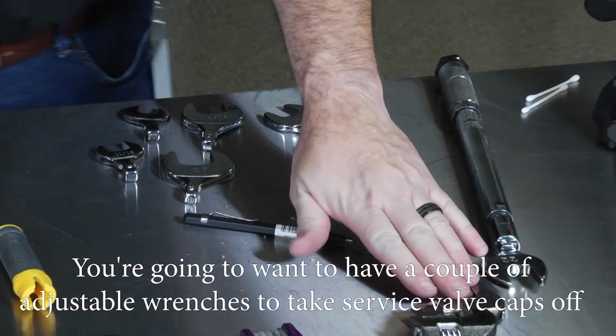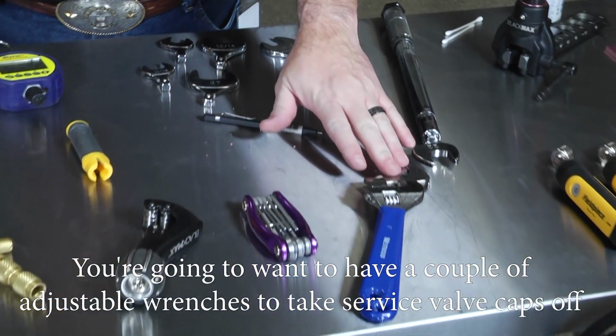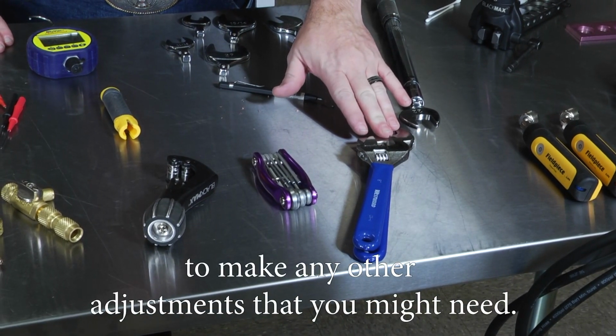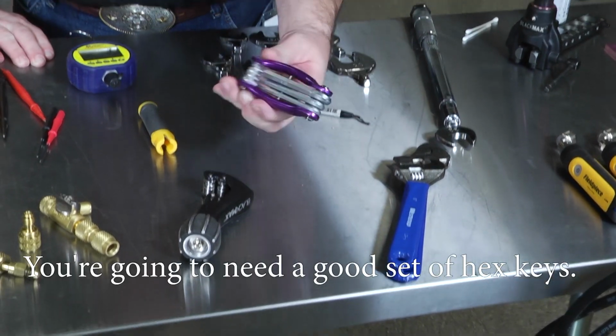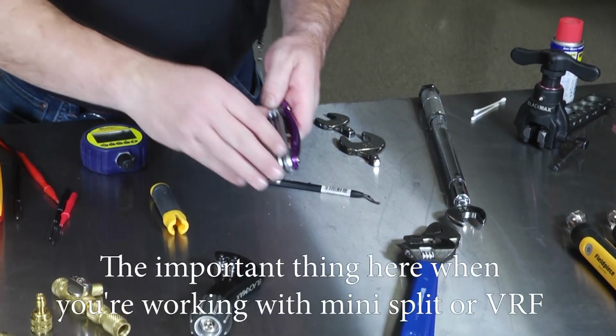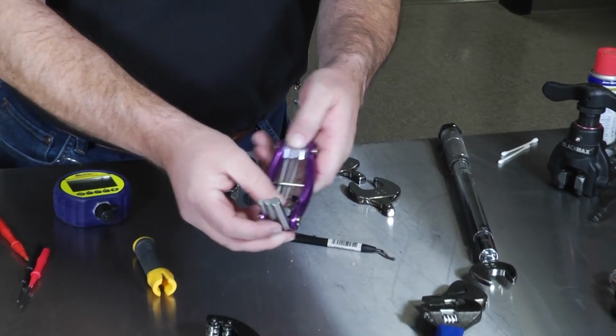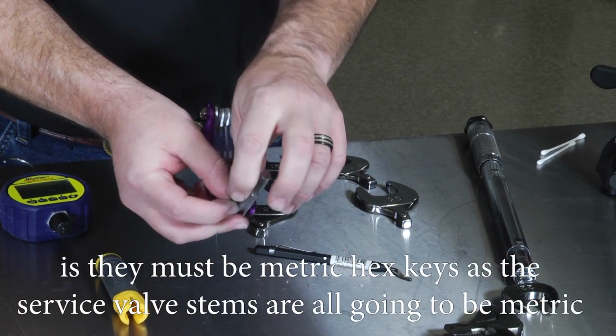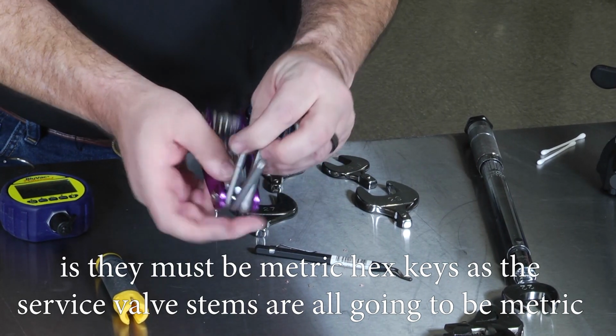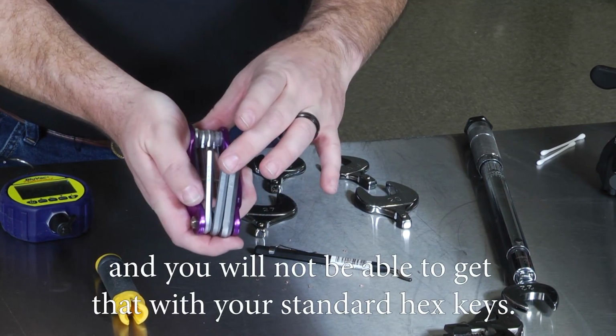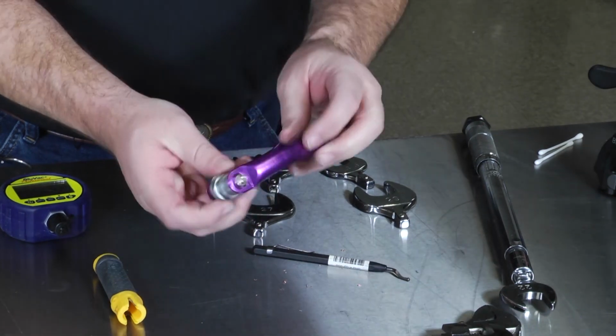You're going to want to have a couple of adjustable wrenches to take service valve caps off and to make any other adjustments that you may need. You're going to need a good set of hex keys. The important thing here when you're working with mini split or VRF is they must be metric hex keys, as the service valve stems are all going to be metric, and you will not be able to get that with your standard hex keys.